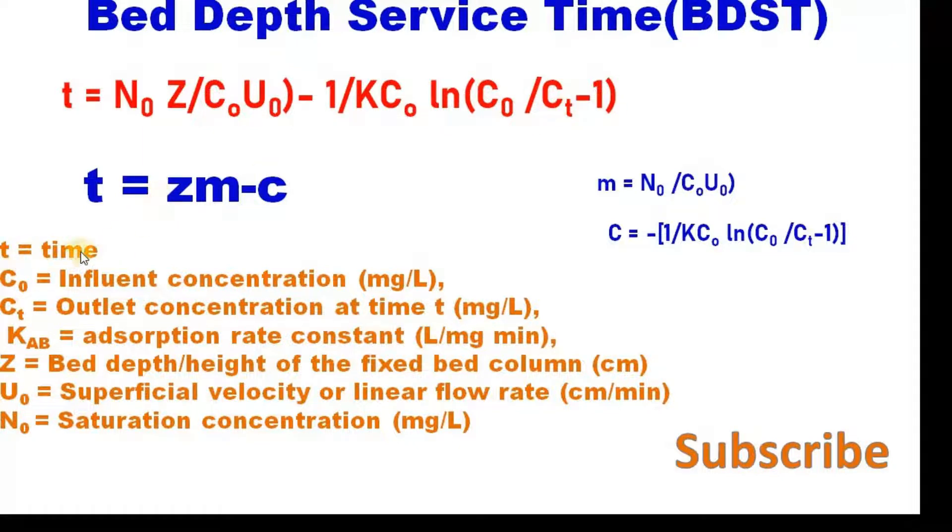Where t is the time, C0 is the influent concentration in milligram per liter. Ct is the outlet concentration at time t. K is the adsorption rate constant. Z is the bed depth or height of the fixed bed column. U0 is the superficial velocity or linear flow rate.